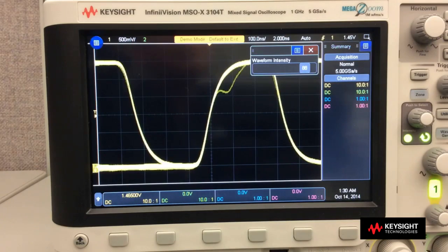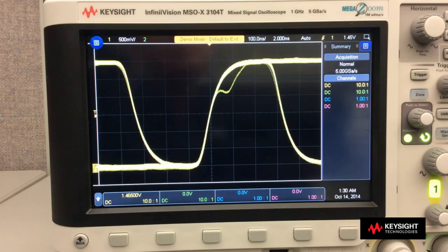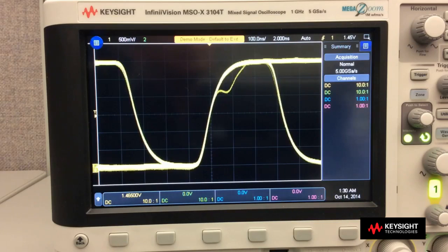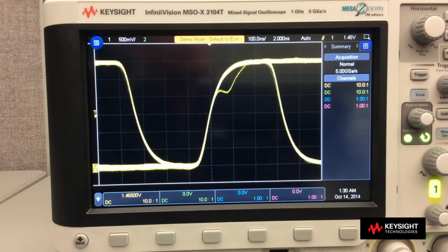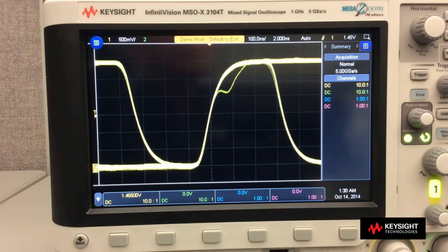The rate of occurrence of this non-monotonic edge is very infrequent. But with this scope's uncompromised waveform update rate of 1 million waveforms per second, this scope can easily capture it.